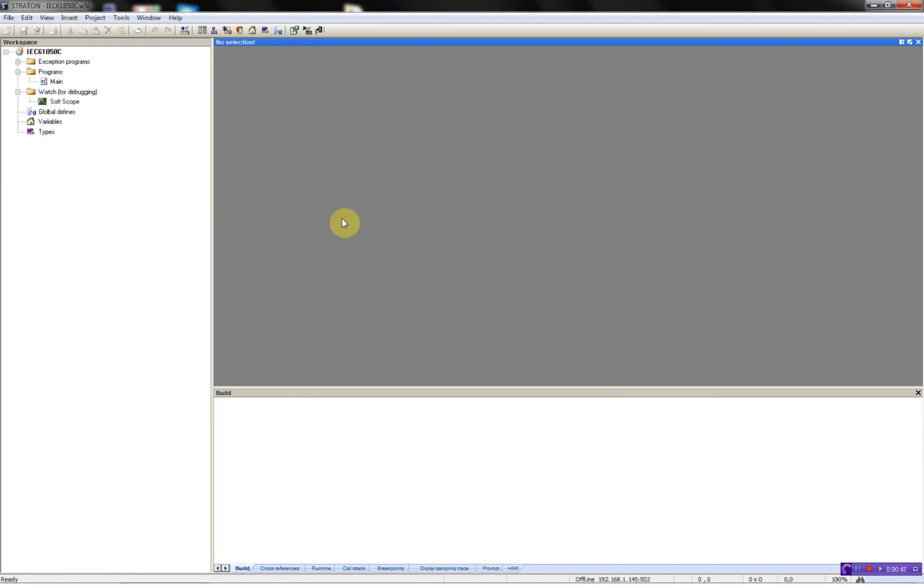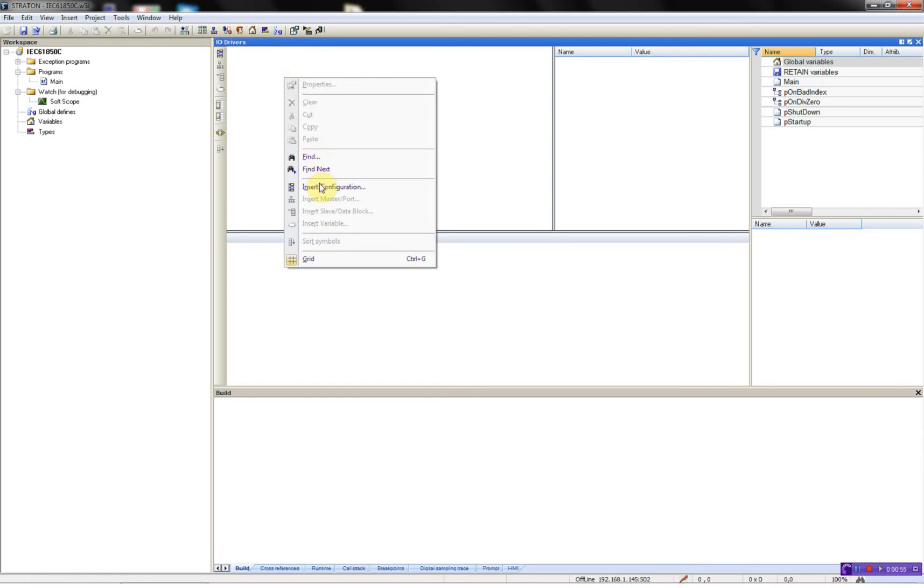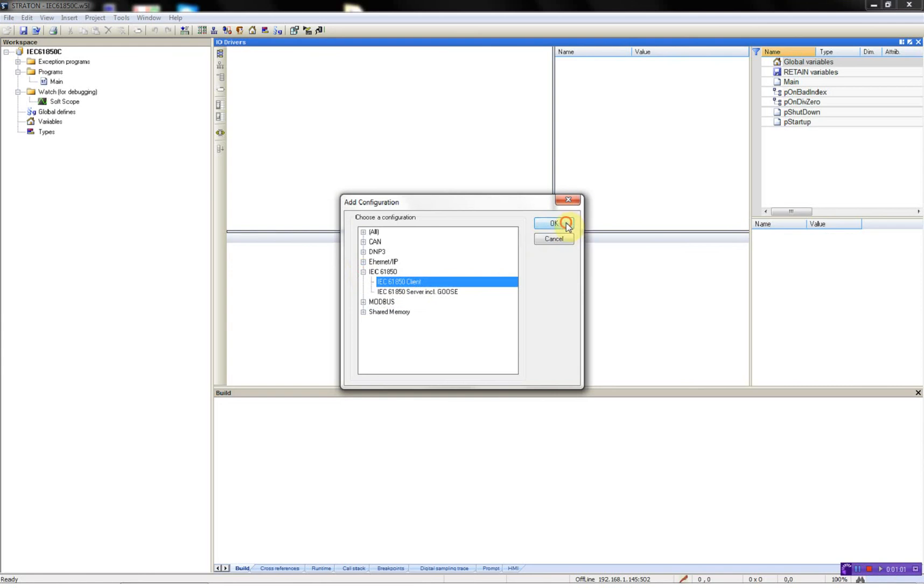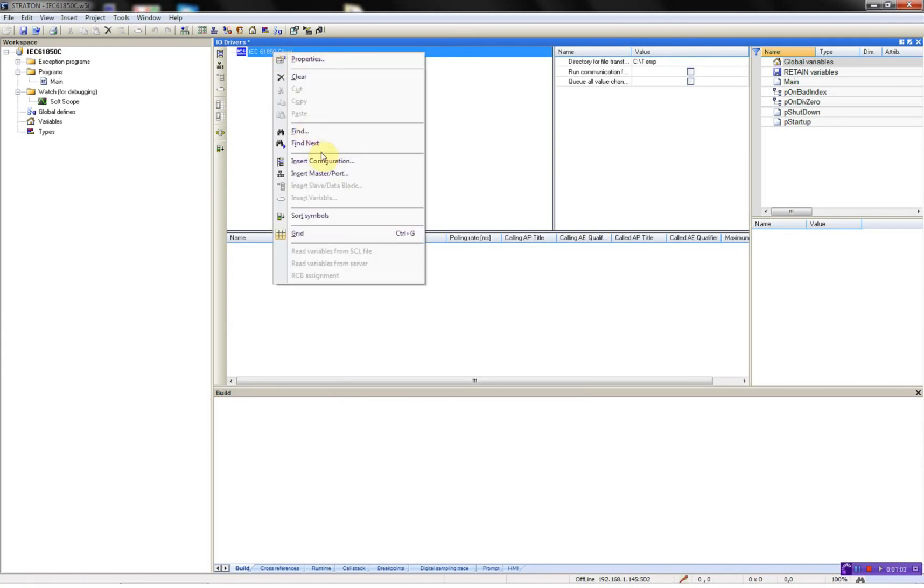So what I need to do now is to configure the driver. This is done in the field bus configurator, so I will start by opening this, then right click, insert configuration, select the IEC 61850 client driver, then right click again, insert master port.